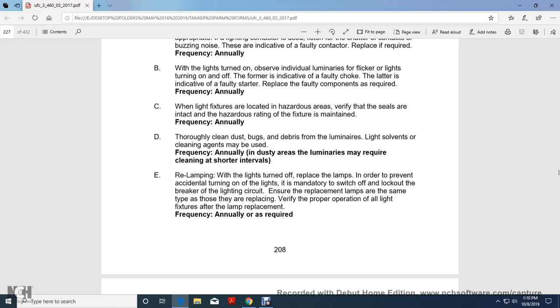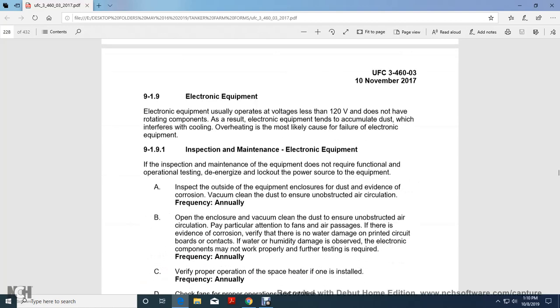Thoroughly clean dust, bugs and debris from luminaires. Light solvents and cleaning agents may be used, frequently, annually. In dusty areas, luminaires may require cleaning at shorter intervals. Relamping. When lights are turned off for lamp replacement, in order to prevent accidental turning on of the lights, it is mandatory to switch off and lock out the breaker of the lighting circuit. Ensure the replacement lamps are of the same type as those being replaced. Check proper operation. All lamp fixtures or lamp replacements annually as needed or as required.